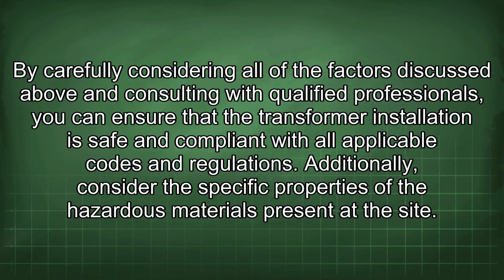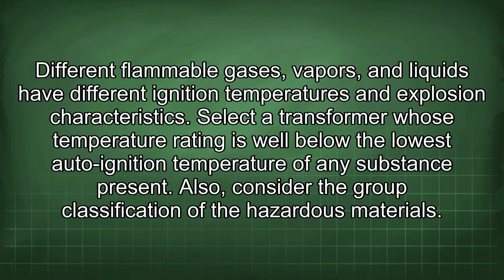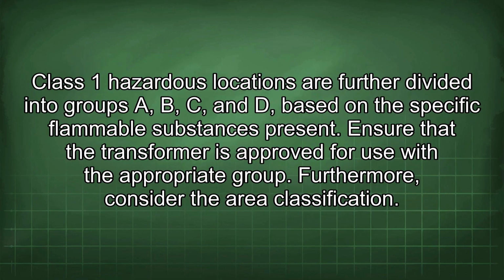Additionally, consider the specific properties of the hazardous materials present at the site. Different flammable gases, vapors, and liquids have different ignition temperatures and explosion characteristics. Select a transformer whose temperature rating is well below the lowest auto-ignition temperature of any substance present. Also, consider the group classification of the hazardous materials. Class 1 hazardous locations are further divided into groups A, B, C, and D, based on the specific flammable substances present. Ensure that the transformer is approved for use with the appropriate group.